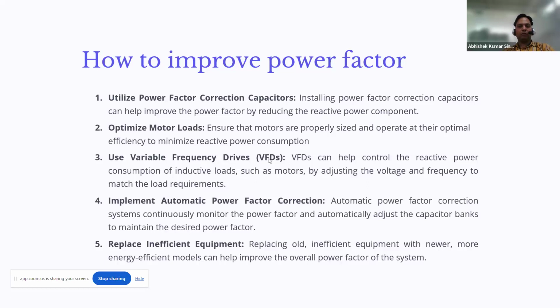So to control the harmonics, we have already discussed that we have multiple systems and how we can control them. One way is replacing the inefficient equipment, whatever equipment is very old, we have to replace it. If we replace that, then the power factor can be improved, because modern equipment has a good power factor.